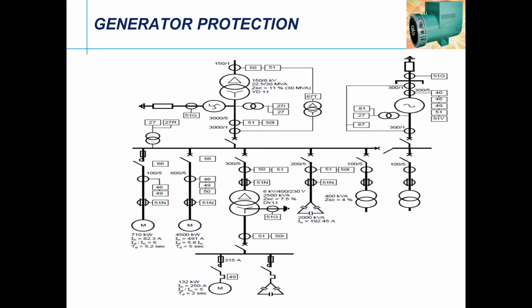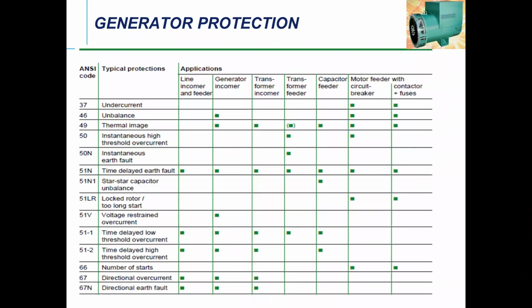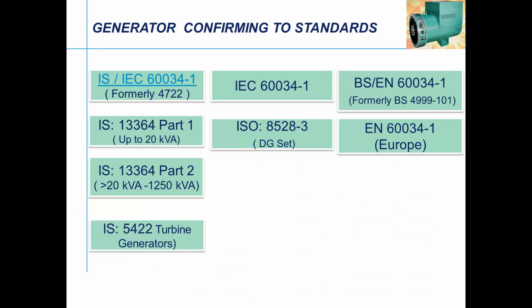This is again generator protection in general, which is not in the AVR but in the system, where you have protection relays: overcurrent relay, undercurrent, unbalance, thermal image, instantaneous high threshold overcurrent, time delay fault and rotor lock current. These are the parameters you had earlier, and today certain parameters are taken care of by our AVR. Today it gives feedback to the system: yes, I have got some problem, please remove me from the system. That is what I am pushing, talking about digital AVR technology.